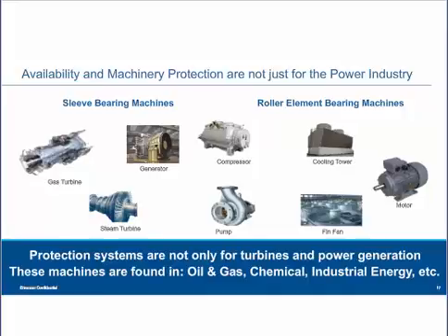Yeah, because whenever you're looking at a plant as a whole, especially plants today that have protection systems, some of the protection systems are outdated. Some have been installed 10, 15 years without much change. So when you look at those systems, again, you have modules for each specific measurement type. So you've got to have a spare, at least one spare. And I think recommendations are generally like 10%. The number of modules that you have, you need 10% of that as your ready spares inventory. So now you're having to maintain these systems. You're having to maintain different modules, different cards in your inventory. And so from a management standpoint, you've got some of your cash flow tied up in product that's sitting on the shelf and not being utilized.